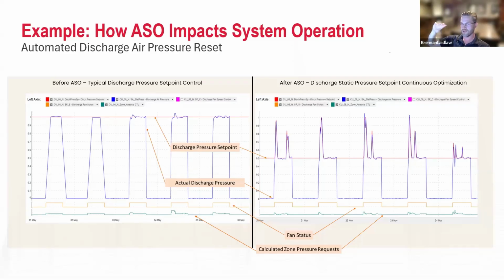So what it will do is it'll send 5-minute set points to the building. Every 5 minutes, you get a new value based on what every zone in the building's doing, how many requests, and it bumps the pressure up and down dynamically. So, one simple example, but you're going to see a lot more of this grow.